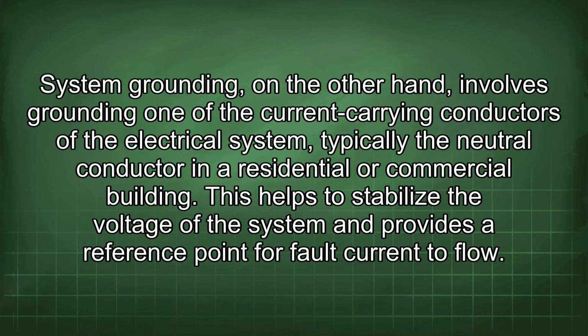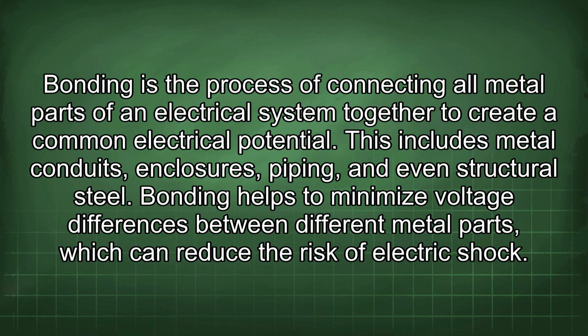System grounding, on the other hand, involves grounding one of the current carrying conductors of the electrical system, typically the neutral conductor in a residential or commercial building. This helps to stabilize the voltage of the system and provides a reference point for fault current to flow. Bonding is the process of connecting all metal parts of an electrical system together to create a common electrical potential. This includes metal conduits, enclosures, piping, and even structural steel. Bonding helps to minimize voltage differences between different metal parts, which can reduce the risk of electric shock.